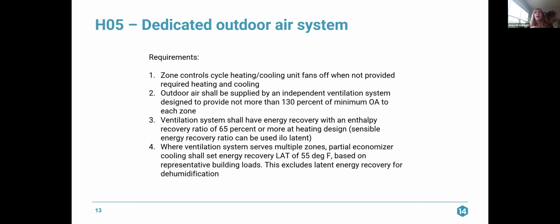Your outdoor air has to be supplied by an independent ventilation system, a DOAS, designed to provide not more than 130% of the minimum outdoor air required by the IMC to each zone. So they don't want you to be over ventilating the spaces. Your ventilation system shall have energy recovery with an enthalpy recovery ratio of 65% or more at heating design. Sensible energy recovery ratio can be used in lieu of latent if you don't have to provide cooling energy recovery or dehumidification.